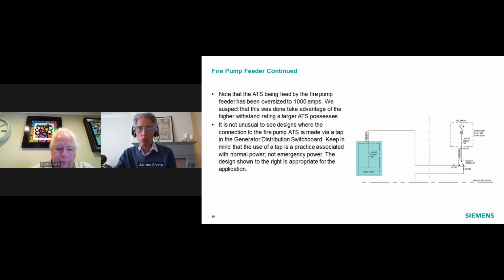So one thing to note on this particular one line is the ATS being fed by the fire pump has been oversized to 1,000 amps. And you'll see it here. And the reason for that is that the fire pump is tapped from the normal side. And you have a fault current there at 69,000. So this switch may be overrated just to accommodate the normal side.